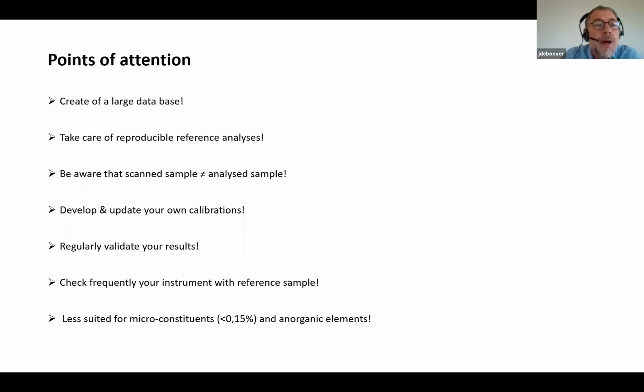And I want to end my talk with some points of attention. It is important to create a large database, to take care of reproducible reference analysis, to be aware that a scanned sample is not always similar to the analyzed sample, that it is important to develop and update your own calibrations, to regularly validate your results, to check frequently your instrument with a reference sample, and that it is less suited for micro constituents and inorganic elements.